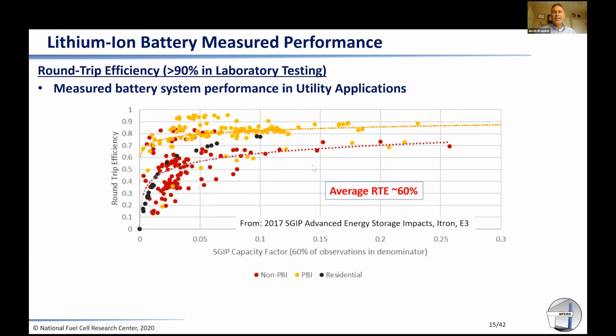What we see is that the average round trip efficiency is about 60%. This was surprising to me, because when we measure batteries in our laboratory, we get greater than 90% round trip efficiency. We know that in utility applications you add transformer losses, converter and inverter losses, but they should never add up to something this low.